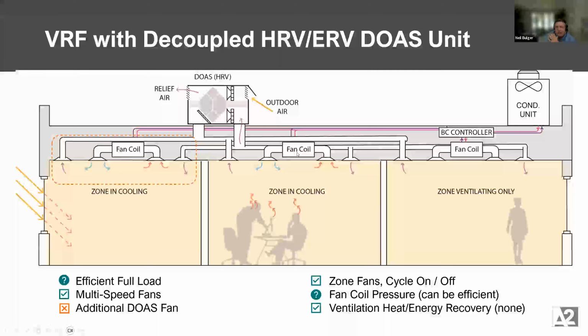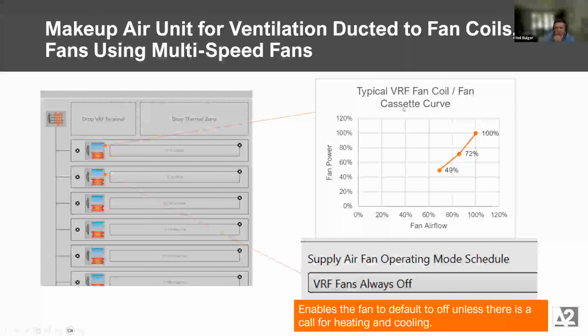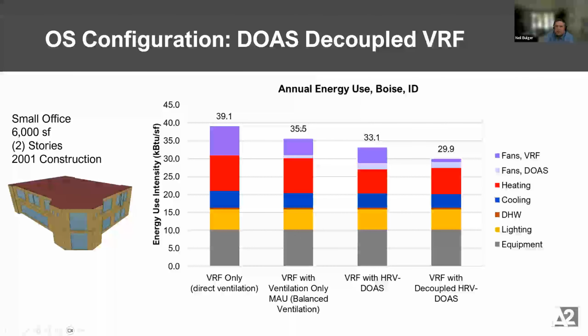We can now let those fan coils turn on and off. We still have our heat recovery device. It has pressure to run. So now we've changed a setting in the software that says, what is the default supply air fan operating mode? This is a fundamental input of the whole fan coil in the software. By default, it's set to always on or always available. And you can change that to say, no, I always want you to default to off. Only if there's a request for heating or cooling can you turn on. By and large, you should only turn on for those requests. And at that point too, you should only be at the speed you need to be at, medium speed, low speed, for the load in the space.